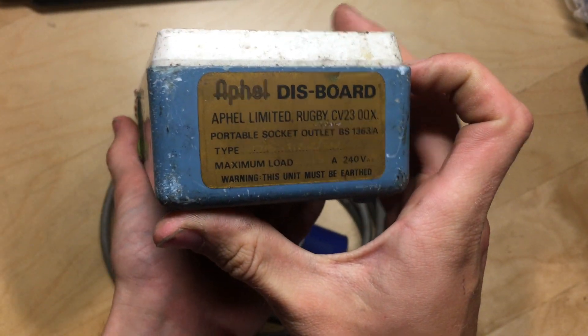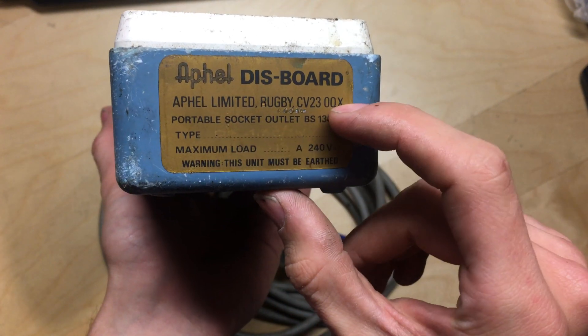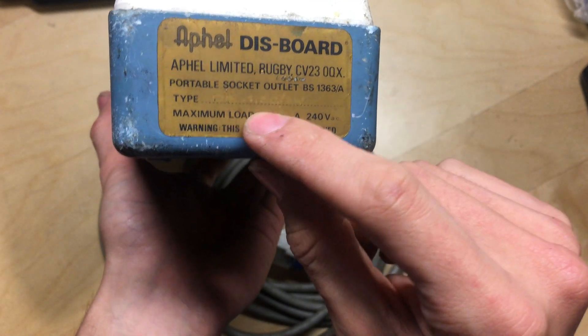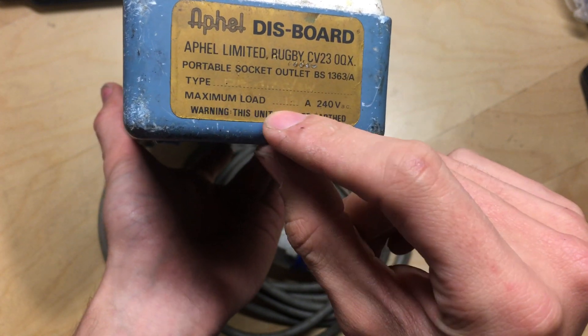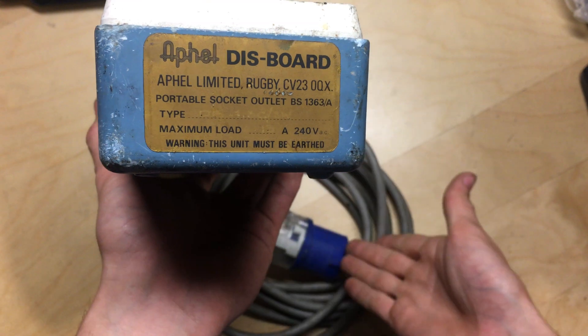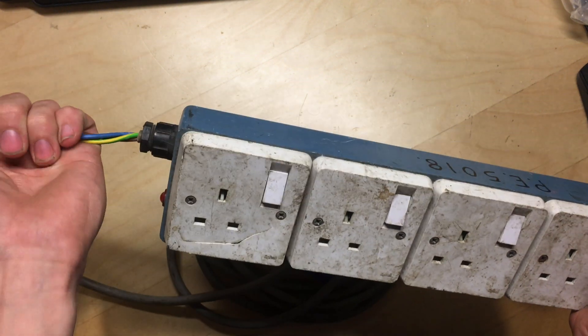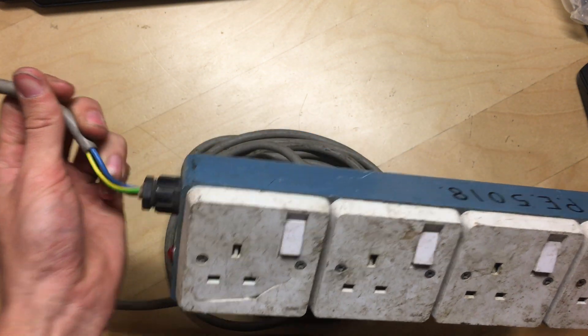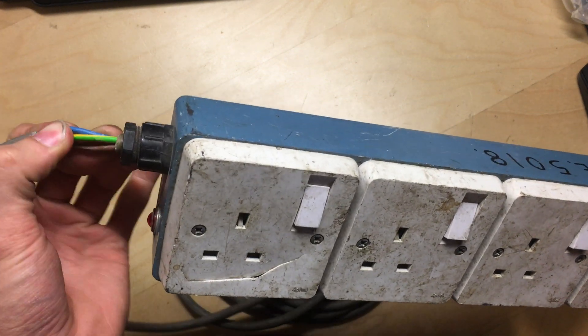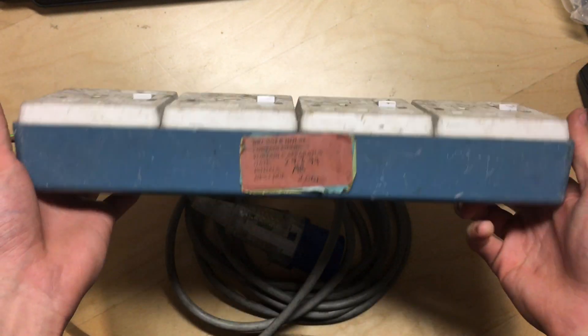This just came out of a unit. It's got branding on it - it's an Aphel Dis-Board, made in Rugby in the UK, portable socket outlet type, maximum load 13 amp. That's because of the size of the cable that's in it at the minute. I'm upgrading this so it'll be able to handle 16 amps - going from 1.5 or 1.25mm cable up to 2.5mm, which is more than capable of 16 amps.